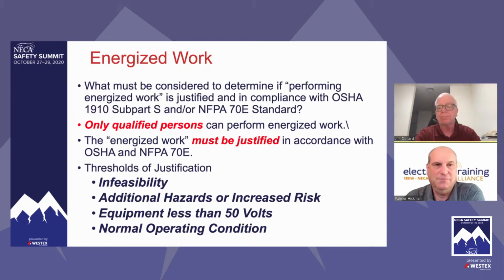Now, on that tool list and on many tool lists today for local unions throughout the United States of America, apprentices are required to purchase and have a solenoid type voltage tester, which is known in 70E as a test instrument. So Palmer, I'm a brand new apprentice and I come on the job with that test instrument, that solenoid type voltage tester. Can I use it? Well, not if you're not a qualified person. And that's one of the key takeaways.